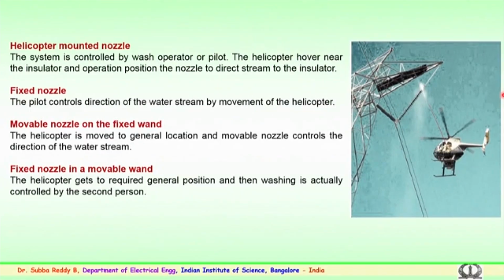The helicopter mounted system, which I mentioned earlier: the helicopter mounted nozzle system is normally used where other arrangements, like the truck mounted nozzles or handheld ones that personnel could use, are difficult for utilities maintenance personnel to reach. In such cases, where the transmission lines or towers are situated on hilltops or in high altitude conditions, or it is very difficult to reach the towers, helicopter mounted nozzles are generally used for cleaning the insulator system. Here the system is normally controlled by the wash operator or the pilot. Generally the helicopter hovers near the insulator string and the operator positions the nozzle to direct the stream of the jet to the insulator.